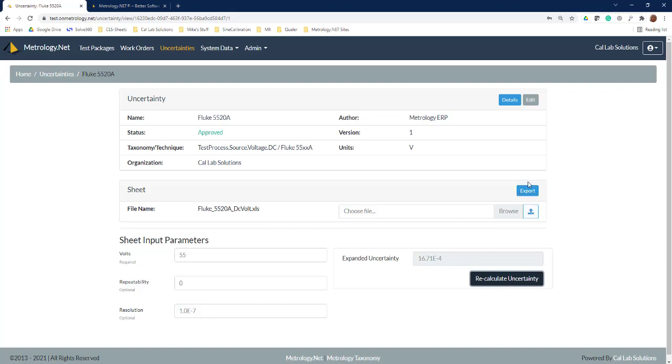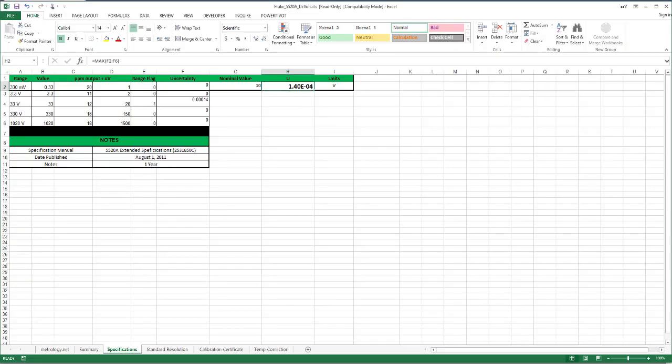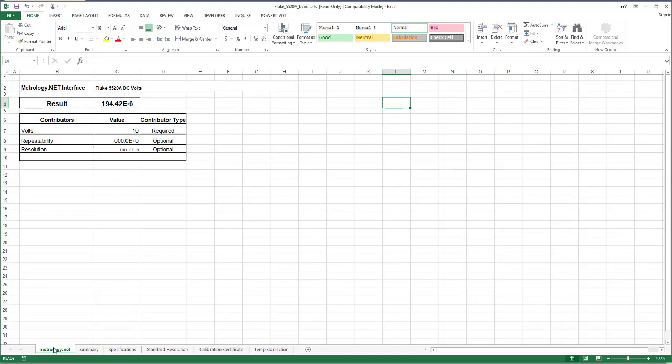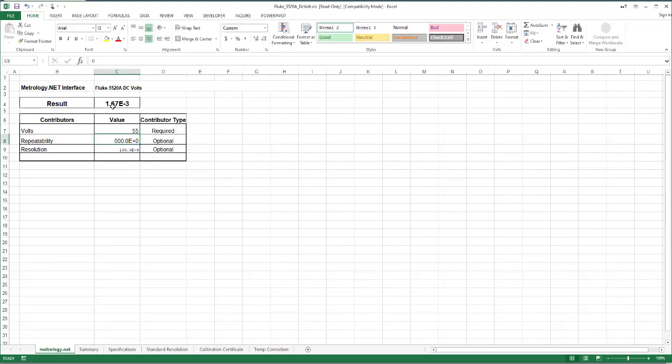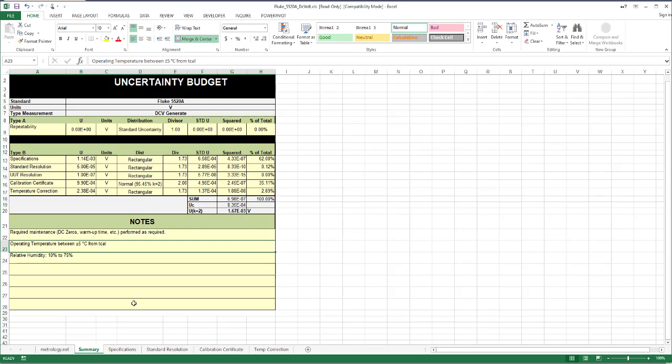You see here it's got 5520 DC volt XLS and then we've got our upload and our export. So here I've got that spreadsheet. If we open up that spreadsheet and do the same thing, come in here and type in 55 volts, you see our measurement uncertainty up here changed to the same value. Now this is just to show how we're doing it, not how to calculate measurement uncertainties. We share all of these spreadsheets out with customers, but you can see it's pretty standard.